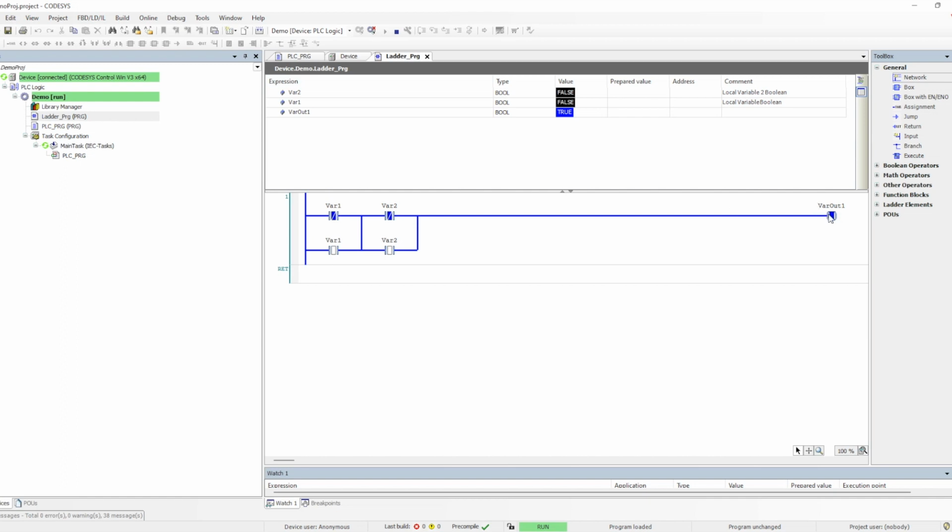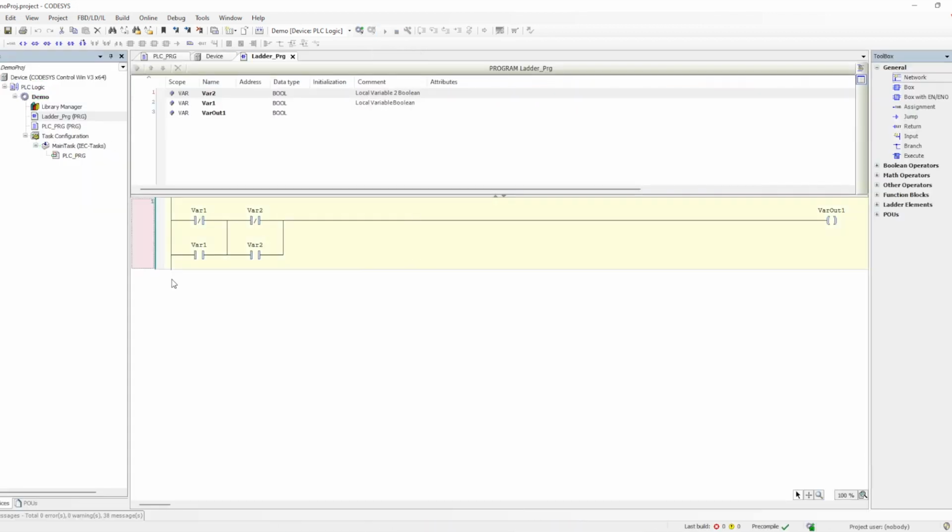So once we go now to the program and see the run, you can see that at the top we had two NC contacts, correct? So once the program started, the rail is energized, and when the rail is energized, it is creating the whole flow path in the run itself. You can see this with the blue line, all the contacts through which the flow is passing are actually shown. Okay, so we can prepare the value and give the command. The shortcut is Control F7. Control F7 is the shortcut to prepare, and after clicking that, it will write it to the particular value.